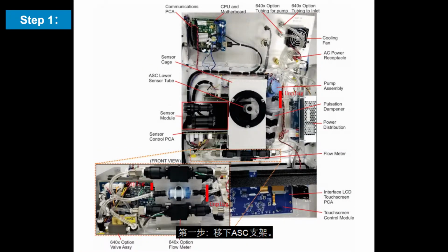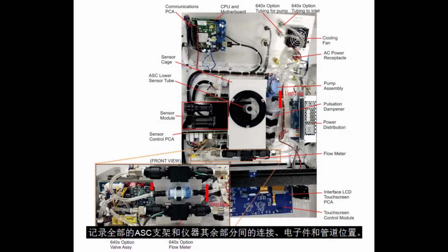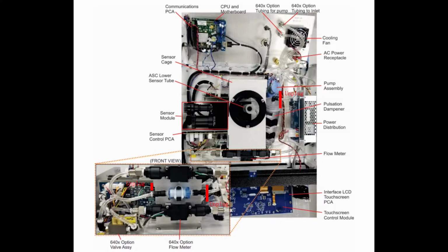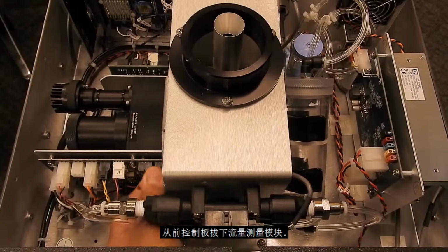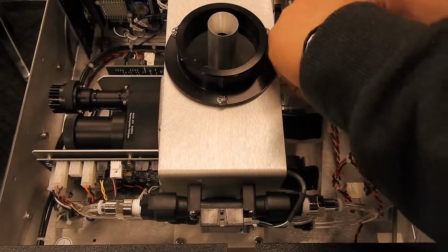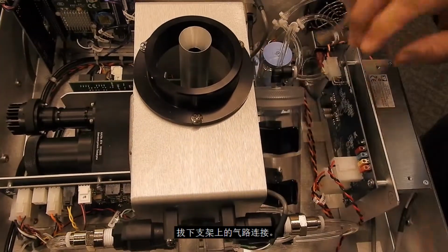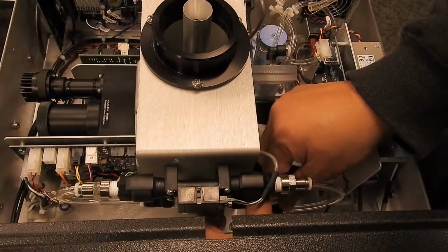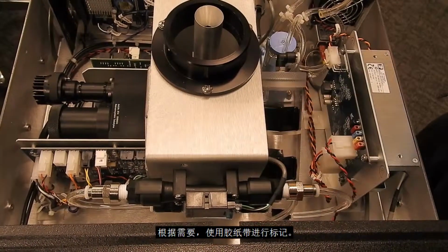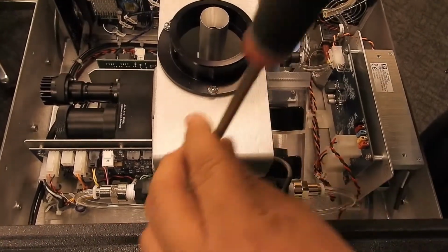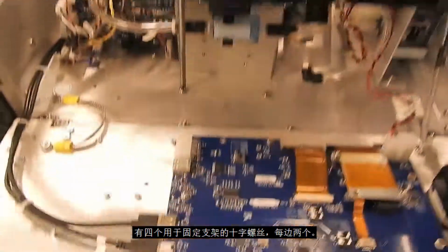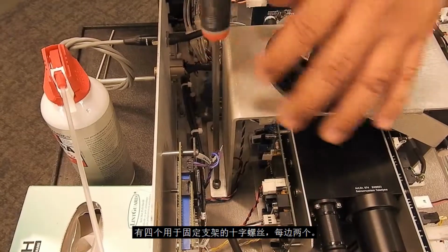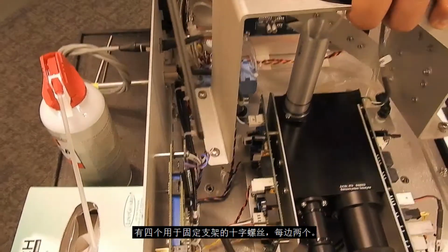Step 1. Remove the ASC support bracket. Make note of all connections, electrical and plumbing, that go between the components on the ASC support and the rest of the instrument. Unplug the flow sensors from the front control board. Unplug the pneumatic connections on the bracket. Mark any connections with masking tape if needed. There are 4 Phillips head screws that secure the support to the floor of the instrument, 2 on each footing.